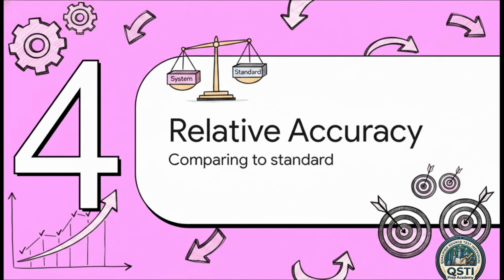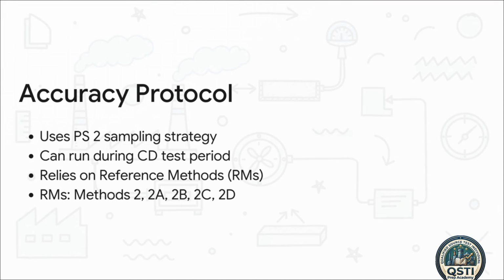Section 4. The relative accuracy test. Because a system can be perfectly stable but still be consistently wrong. Let's look at the second exam. The relative accuracy test protocol is where we see how accurate the system is compared to a totally independent, proven standard. The sampling strategy here?